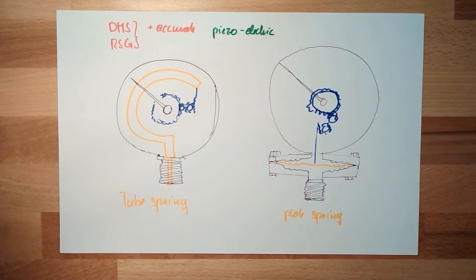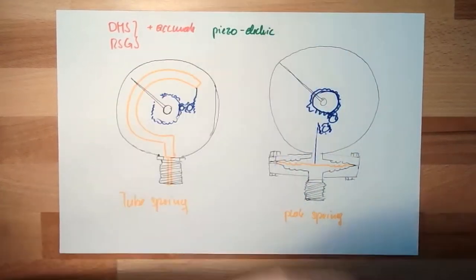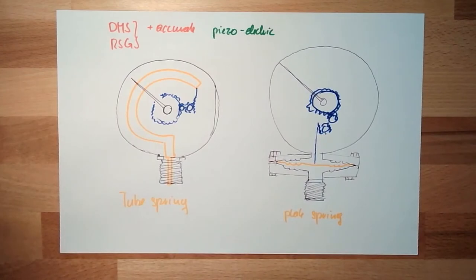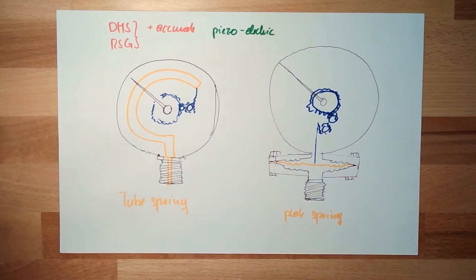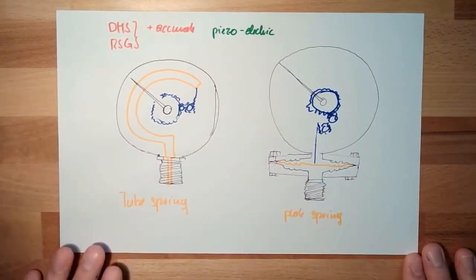Disadvantages of piezoelectric devices: they tend to drift. So if you have static pressure, piezoelectric sensors are not that accurate, because they tend to drift a little bit. For dynamic pressure they are perfect; for static pressure they are not that perfect. Also, you need special cables and special charge amplifiers — there is more required around this piezoelectric measurement.